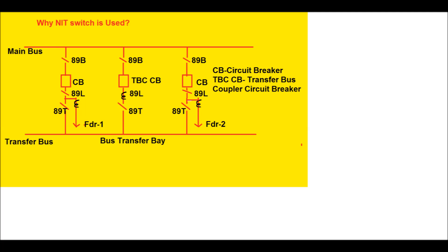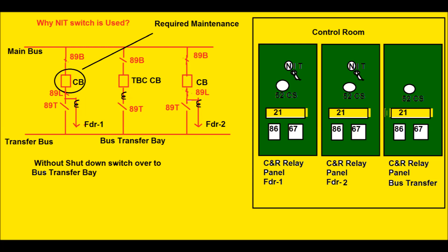Now, to understand the uses of the NIT switch, let us take a simple example as shown in this single line diagram. Here there are two feeders and one bus transfer bay. There is one main bus and one transfer bus. Feeder one is supplying power through closing of 89B and 89L and the closing of the circuit breaker of its own bay. 89B is the main bus side isolator, 89L is the line side isolator, and 89T is the transfer bus side isolator.